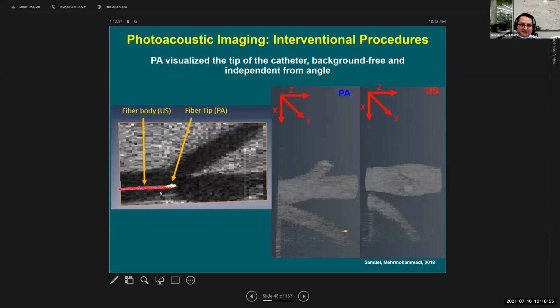This is a photoacoustic image combined with ultrasound. The ultrasound image shows the whole fiber or catheter, while the photoacoustic signal is only generated at the tip of the fiber. So I can basically see where the tip is located, where the body of the catheter is.